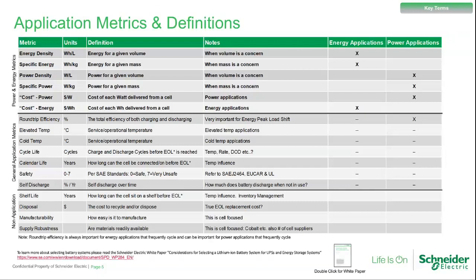It's about augmentation and replacing modules to keep that performance guarantee. It's also, as Richard discussed, the cooling load on the system. That load will actually increase over time because as batteries age, most have an increase in internal resistance, which lowers round trip efficiency, generates more heat, and puts more load on the HVAC system.